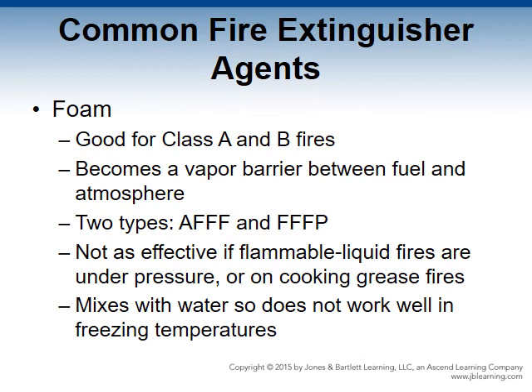Foam is a good agent for Class A fires and an even better agent for Class B fires, because it creates a vapor barrier between the fuel and the atmosphere, suffocating the fire by preventing oxygen from mixing with the fuel. To make foam, the agent is discharged through a special aspirating nozzle to mix with air. There are two types: AFFF (aqueous film-forming foam) and FFFP (film-forming fluoroprotein). NFPA 10 states foams are not as effective on flammable liquid fires under pressure or on cooking grease fires. Foam mixes with water, so it does not work well in freezing temperatures.